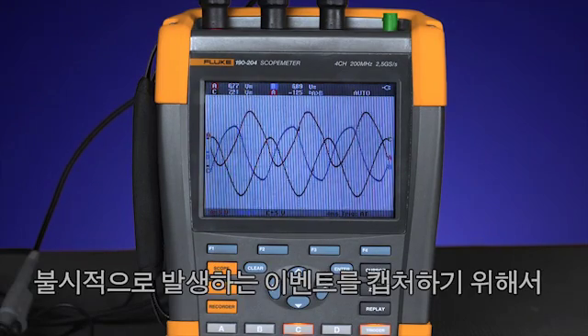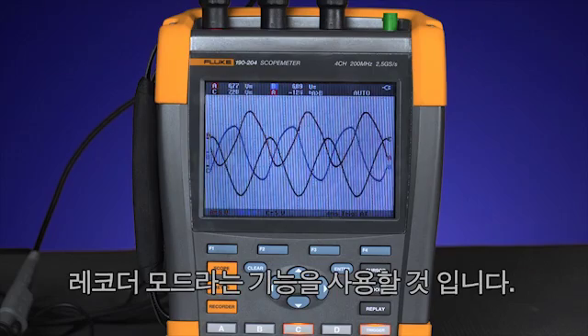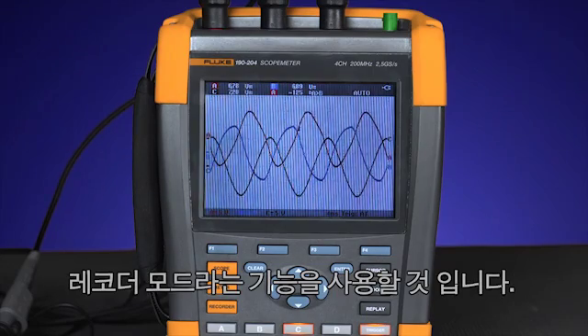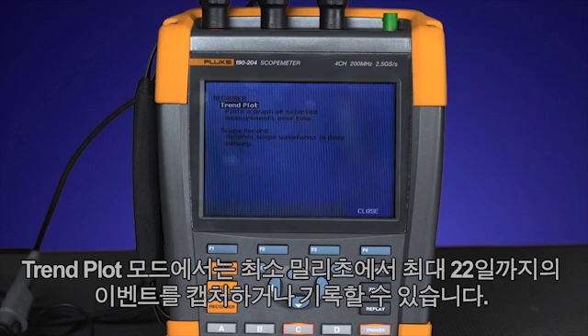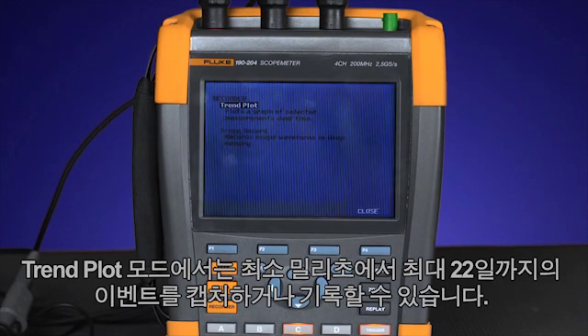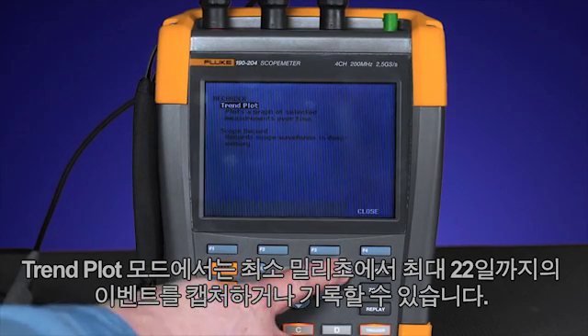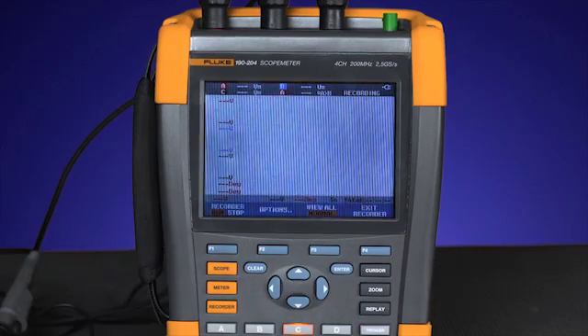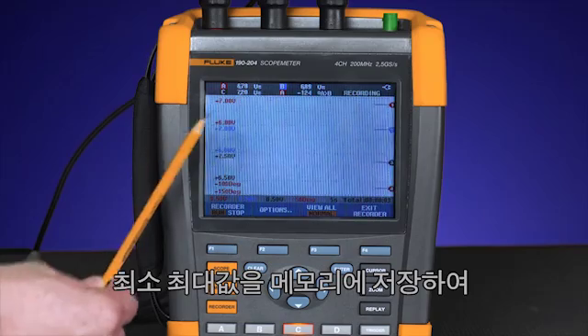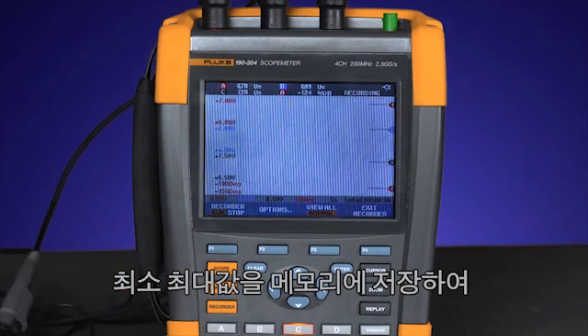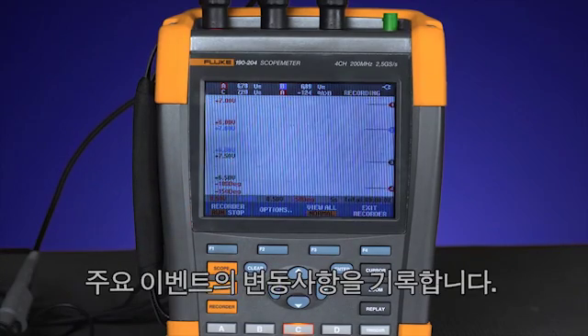In order to capture a random event, we'll use the function called recorder mode. In trend plot mode, you could capture or record events from as little as milliseconds up to 22 days. The oscilloscope will acquire the input signal, measure the values, and store the min-max values in memory, holding major event changes in record.